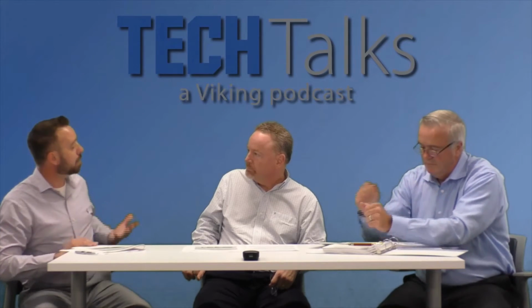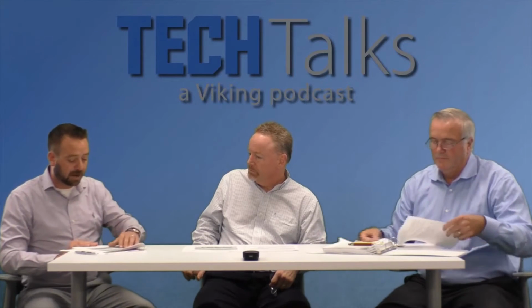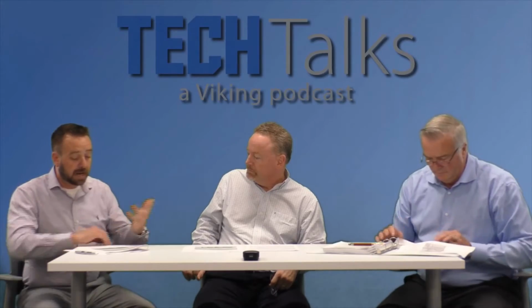There's also been provisions for eliminating 8 feet, 12 feet, even 35 feet in some examples. So in this case, if you're over 30 feet, you automatically have to go up to 40 feet now in this situation. And we can also see that with the table revisions, now instead of the 12 sprinkler design, we're going to the 9 or 10 sprinkler design in most of the scenarios.